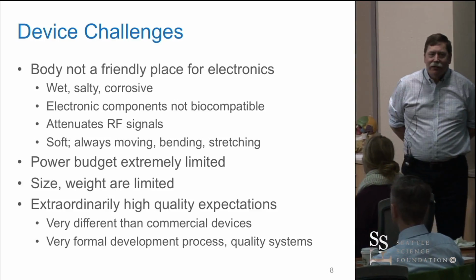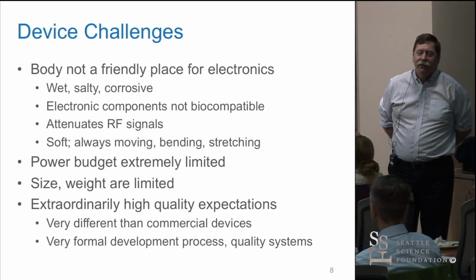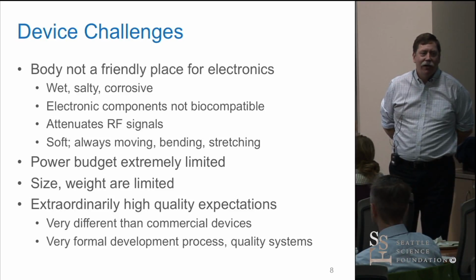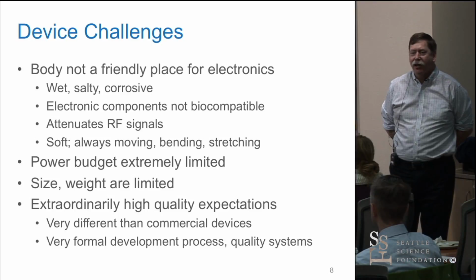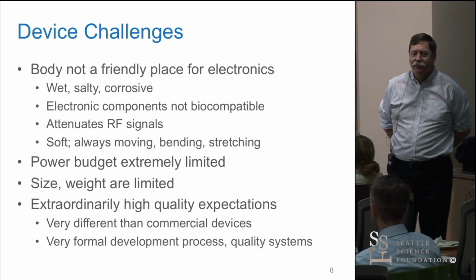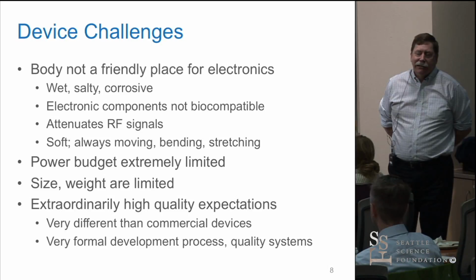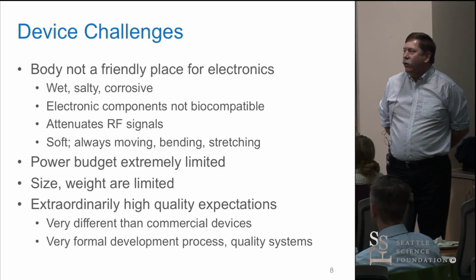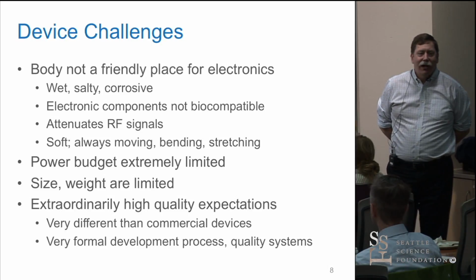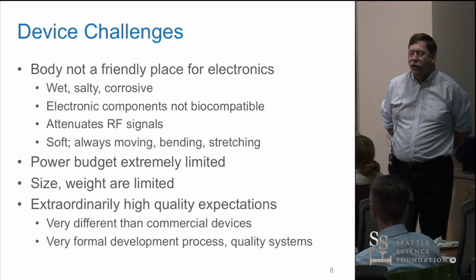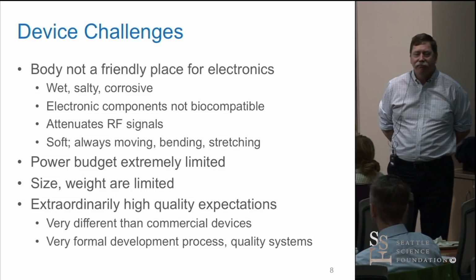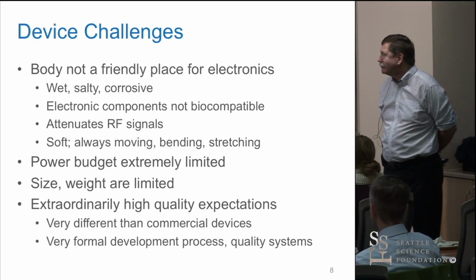Other issues with putting active devices in the body. So these days we'd like to be able to get data into and out of the device, and the preferred method of doing that, like we move data around all the time, is with radio frequency signals. The frequencies that your cell phone or your wireless router operate at don't propagate through the body very well. The body tends to start attenuating things above several hundred megahertz, so that's a problem for us, and we have to adapt to that.